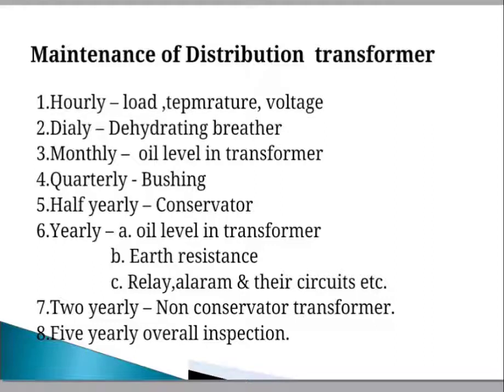Because of that, we have to check the dielectric strength of the transformer oil. Then we have to check the acidity and sludge test. If the results are good, then the oil is properly maintained. If the results are bad, then we have to purify the oil and remove the sludge contents present in the transformer. It will affect the dielectric strength.